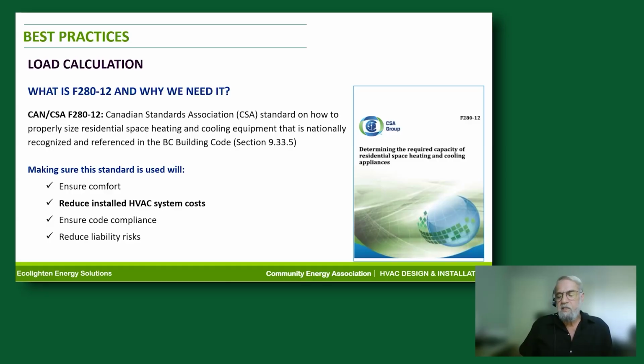F280-12 is the CSA standard method, the methodology to discover what the heating and cooling loads are, and the equipment capacity requirements. That's the methodology, and it's in section 9.33.5 of the building code. It's actually required. It's crazy not to do this on a project. Luckily it's getting more common that it is done, but rule of thumb sizing still happens. It's nuts not to do this.